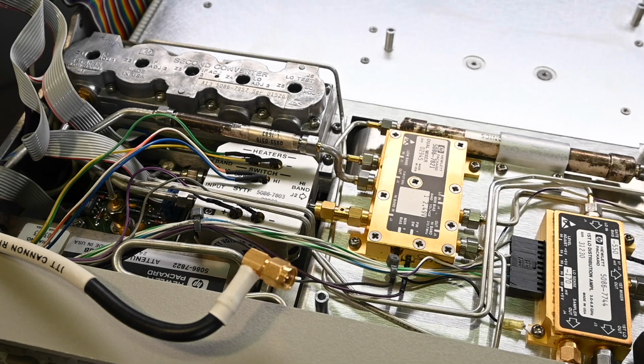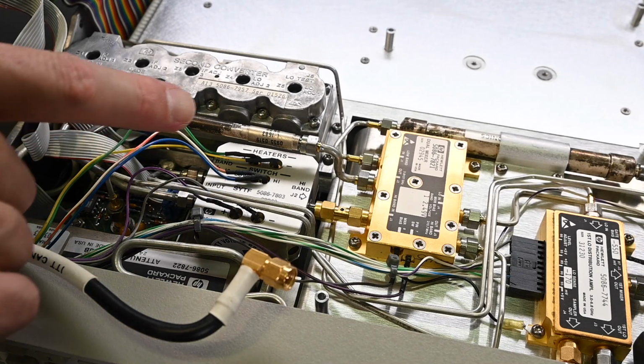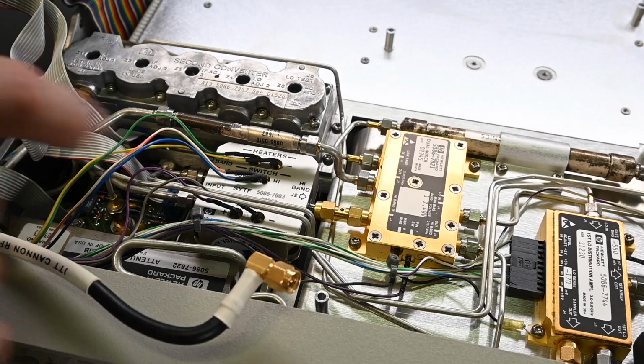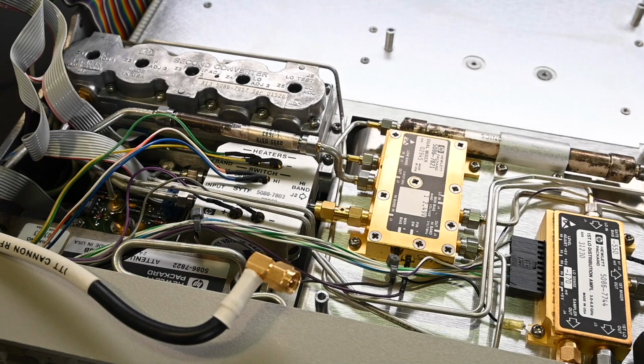So we want to make sure that the low RF band is working the way that it's supposed to, because of course that's where the problem was initially. And we'll also look at the high RF band, but I suspect the high RF band may have some errors because it hasn't been calibrated yet. But if everything looks like it's working close to the way that it's supposed to, then we'll move on to the calibration procedures. So the calibration for the A10 module affects the YIG tune filter, and the YIG tune filter is only used on the high RF band.